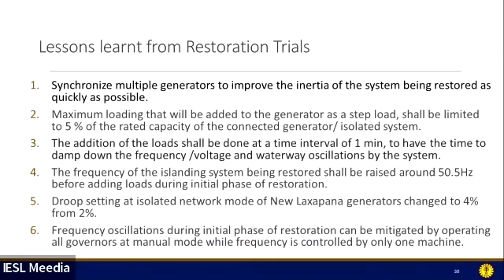And then, when we observe frequency oscillation during the restoration, the governors of those oscillating machines have to be put into manual mode. So operators are well aware of those things after carrying out the restoration trials. The mistakes that happened in 2020, we took corrective actions on, and that was implemented very successfully this time. So this is how we restored the system.